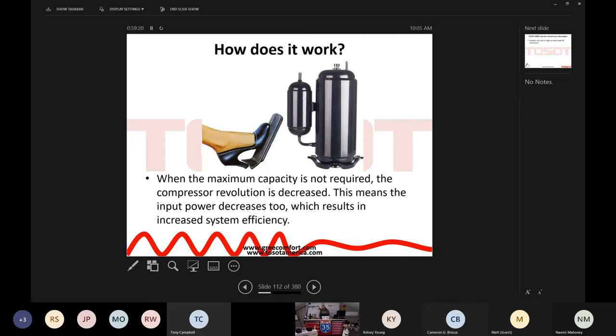And when the system finds the sweet spot, and what I'm calling the sweet spot in this context is her set point temperature, whether that be 68, 70, 72 degrees, once the system finds and establishes that sweet spot, well, then, baby, it is cruise control. Now we're just maintaining the revolutions of the compressor to maintain that set point temperature. Guys, does that make sense? I hope it does. I think it's a beautiful way, not only for our customers to get their head around the concept of an inverter modulating compressor, but also for us, right? I think we all have a good understanding of the automobile. It's a great analogy to make.